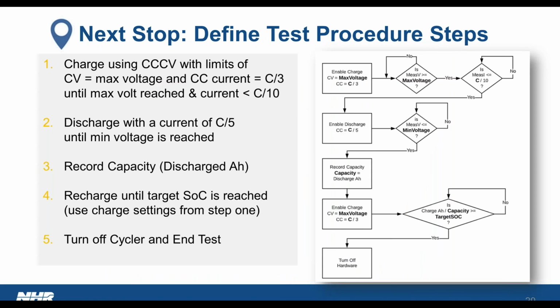Our next step is to define the test procedure in terms of all the individual steps used. For example, step one would be to charge the battery until it's full. From the manufacturer, they would say to charge the battery up to a constant voltage equal to the maximum voltage and a current equal to the capacity of the battery divided by 3, or a 3-hour rate.